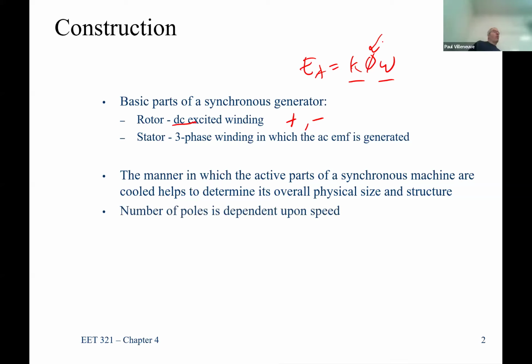So, number of poles or pole pairs, right? Because we only have an even number of poles, that is going to determine what the speed is. And believe it or not, the speed is determined by our mechanical engineering friends, because they have to do all their work to optimize their mechanical system. They know, I can run this generator at 3,600 RPM, 1,800 RPM, 1,200 RPM, et cetera. So they're the ones who have to figure out what the mechanical system needs to be rated for. We as electrical engineers will only focus on, okay, you need it to be 1,800 RPM, then I know I need a 4-pole machine. 1,200 RPM, I need a 6-pole machine.